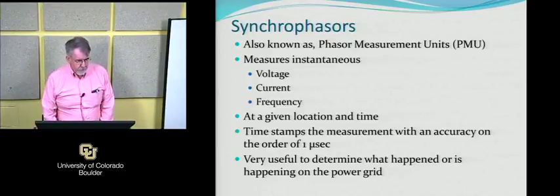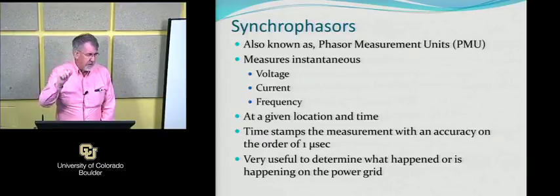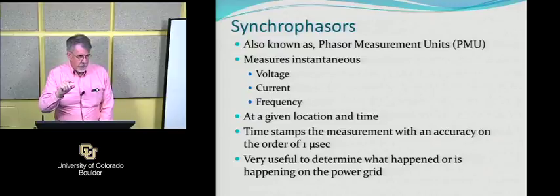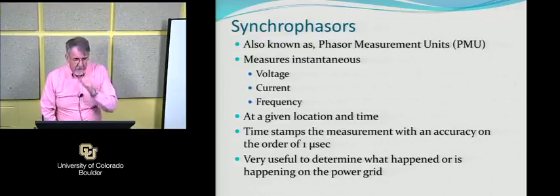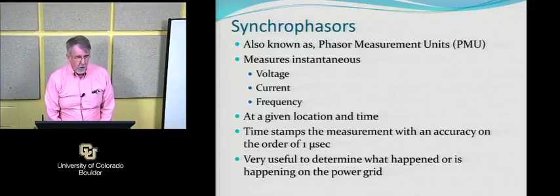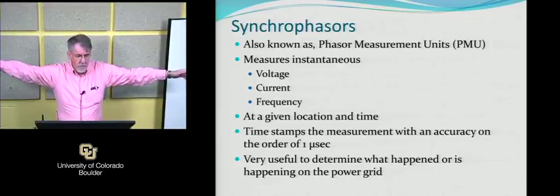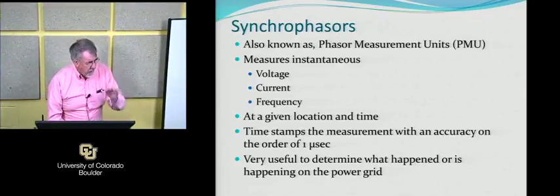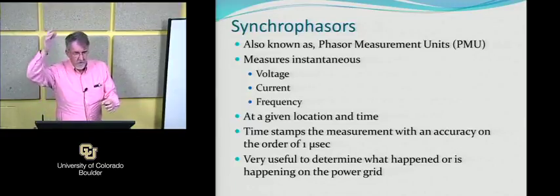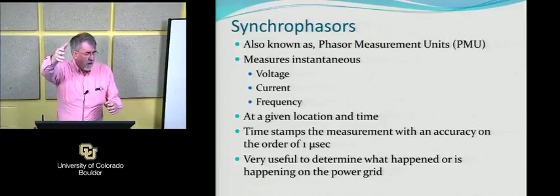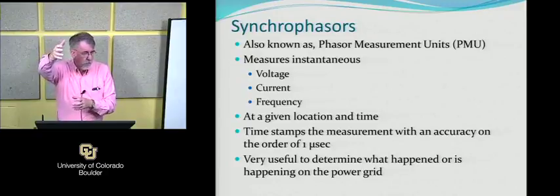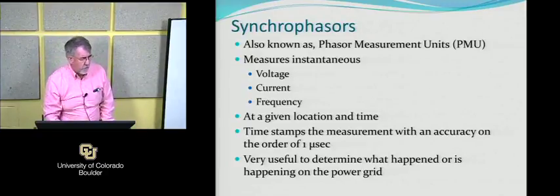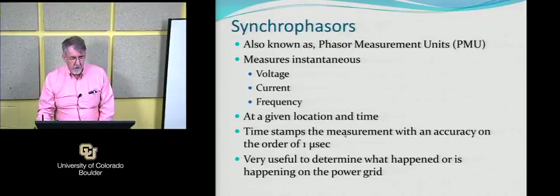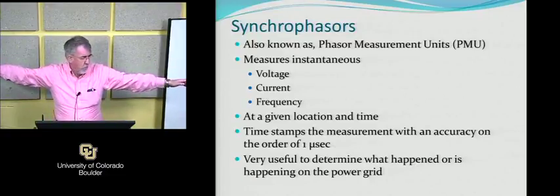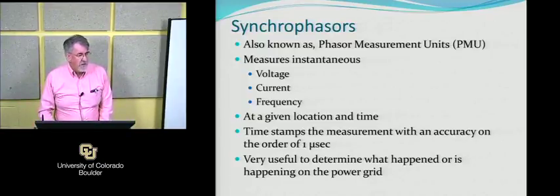So they will give you a measurement and a very exact time of when those measurements were valid. And the time tends to need to be within about a microsecond. So all these units out here are measuring voltage, current, and frequency, and they're not doing it at exactly the same time, but they are doing it synchronized to a master clock, and there is less than a microsecond of error in when they make the measurement. So they timestamp it with this 1 microsecond. Now you get a whole bunch of measurements over the power grid that you know exactly when they occurred.